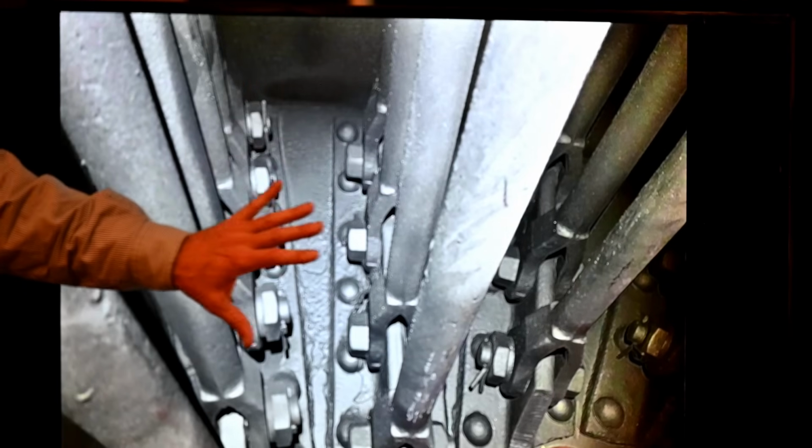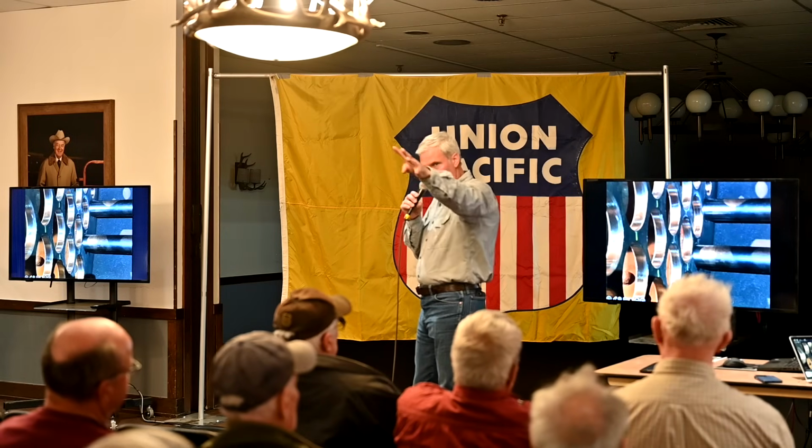All of these giant braces, you can't quite see them the way the picture is taken here, but these are giant forged rods of varying lengths, and they all attach to what we call the unstayed surface. So any of this stuff here, above the area, the tubes themselves actually are attached in a way that holds one tube sheet and the other one together. Those are stayed, so that's a stayed surface. This area here, had it not been for these, would be unsupported, and there's no way it could withstand the pressure. So all of these structures here, when you're laying in there, they're all varying lengths, and some of them go all the way back to the dome, and they're all in a nice symmetrical radial pattern.